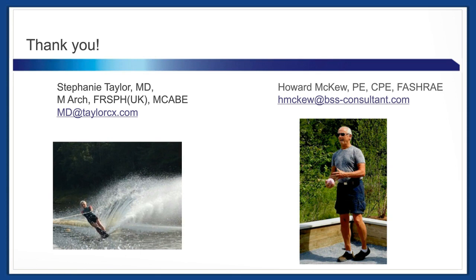So I think this one would be Howie. What should be the fresh air percentage? Is that something that's standardized? Well, again, the ASHRAE guidelines indicate how much outdoor air should be introduced into, say, a patient room versus an operating room. I think recent studies are focusing on how to reduce that outdoor air. I know that, say, in an operating room, it used to be standard that you ran it 24/7 at anywhere from 15 to 25 air changes over the past several years.